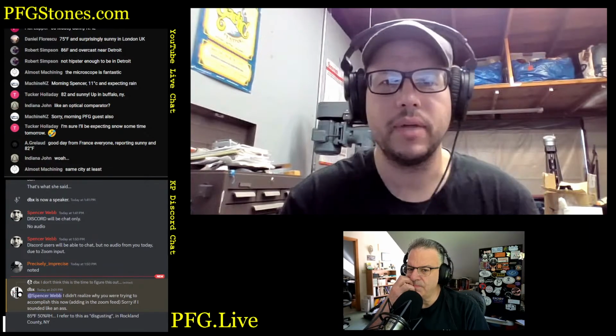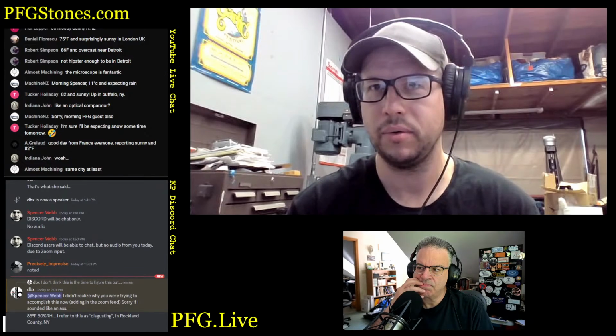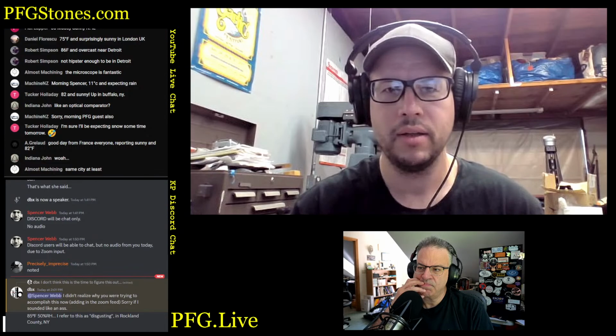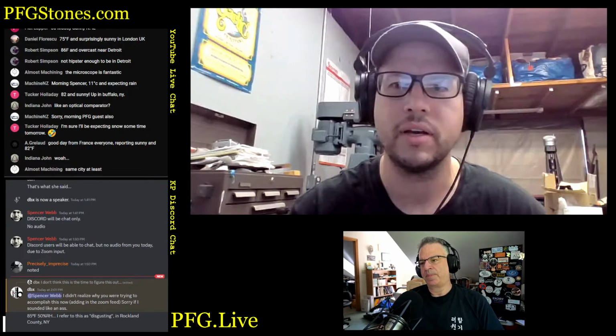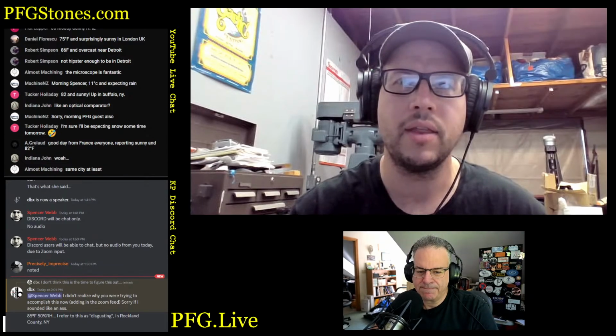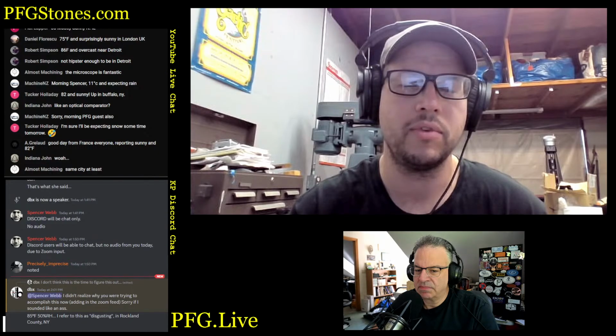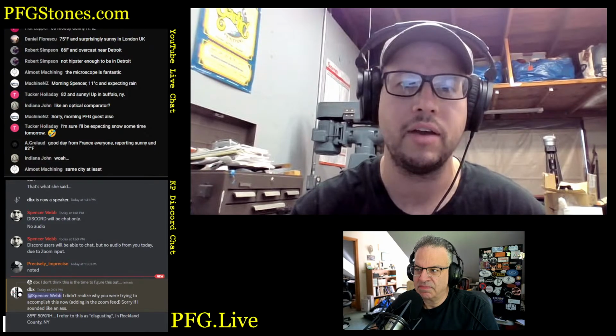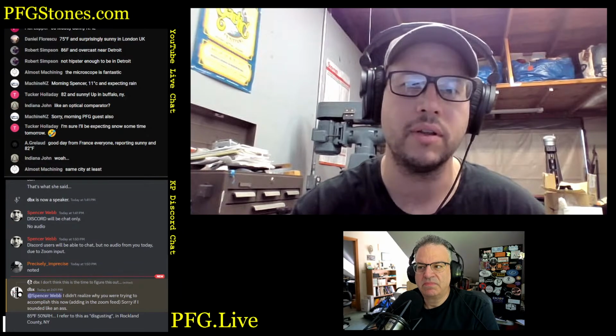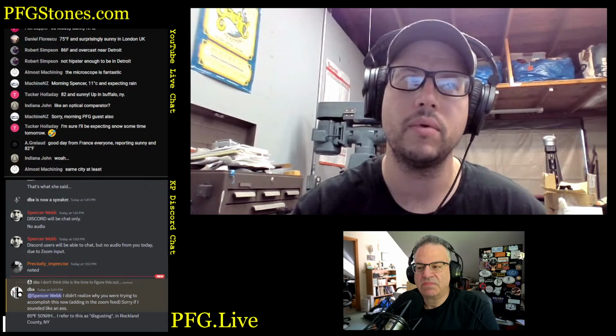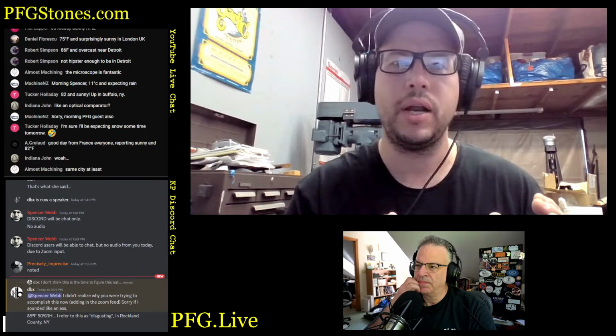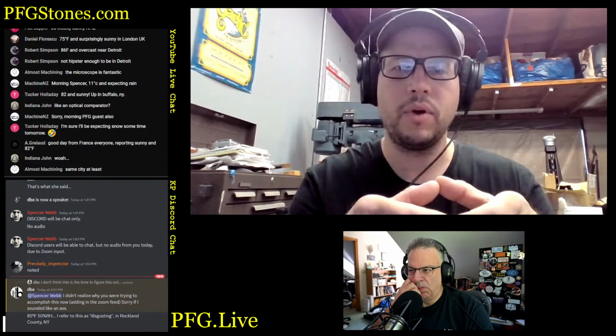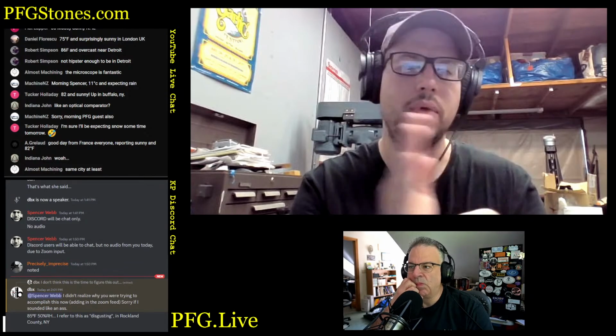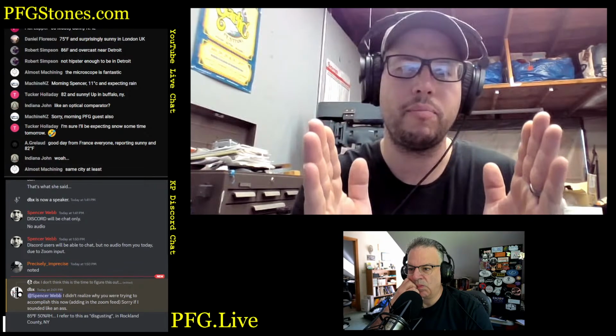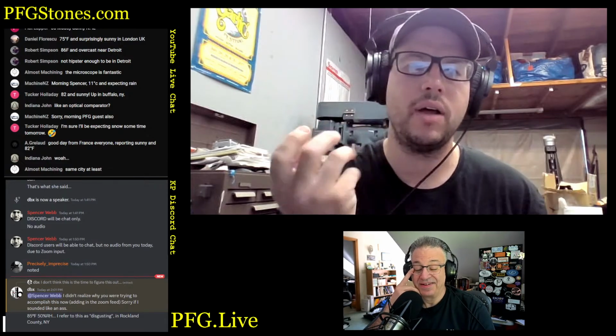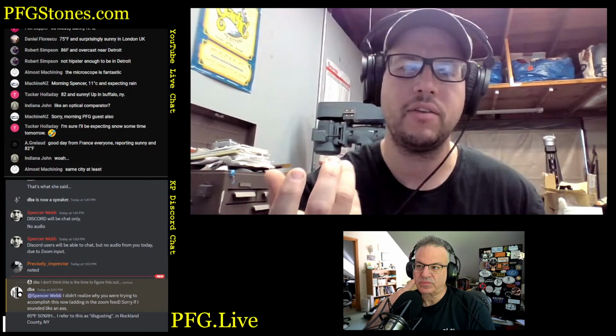I mean, the glass scale is a mechanical measurement, right? So how exactly it factors into the optical system is not super clear to me. There are three systems that need to be linked up for this thing to work. There's the glass scales, the objective lenses themselves, and more specifically their exact magnification, and then the CCD sensor in the camera. When you calibrate this thing, the scales get calibrated, but you also have to calibrate using one of those low reference microscope slides. You have to calibrate a known distance and link it up to a certain number of pixels that it covers on the CCD with each objective, so that you link the pixels and the magnification of each objective.